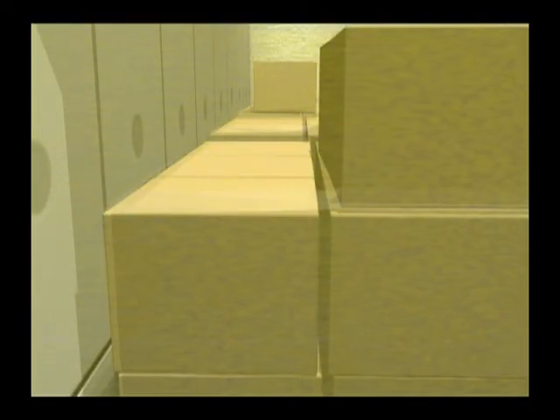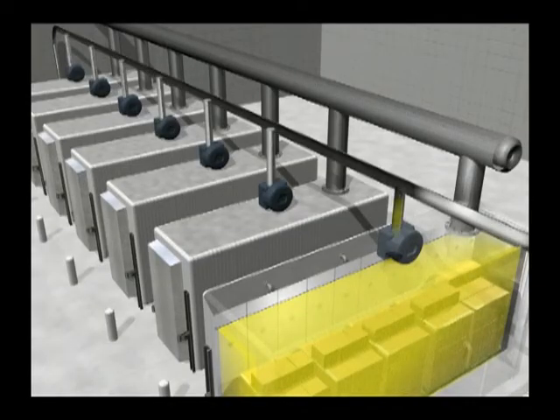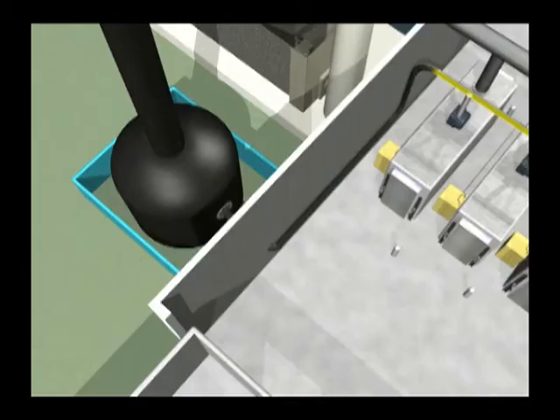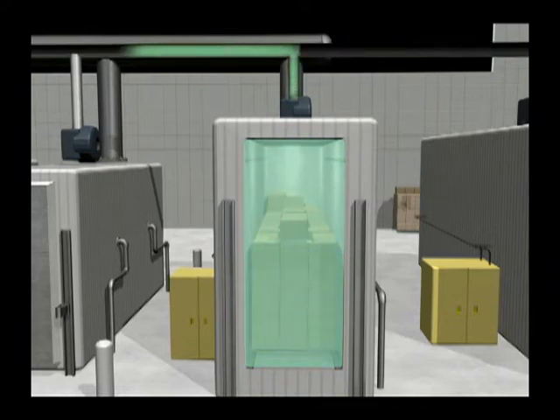After the sterilization phase, ethylene oxide is removed from the chamber and the packaged products in several steps. First, about half the gas is pumped from the chamber to a pollution control device called a scrubber, where it is removed by chemicals. Next, virtually all of the remaining ethylene oxide is removed in a step called gas washing. This involves injecting air and nitrogen into the chamber, where they mix with the ethylene oxide, and this mixture is then pumped from the chamber to the scrubber.